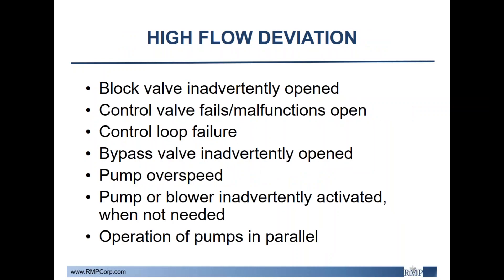Moving on to the high flow deviation. Some common causes here are block or control valves being fully opened, control loop failures, or a bypass valve being inadvertently opened. There are also a number of things that occur with pumps or blowers, such as pump over-speeding or being activated when not needed. Facilities also often have pumps operating in parallel with only one operating at a time, so if both were activated that could also create a high flow scenario.